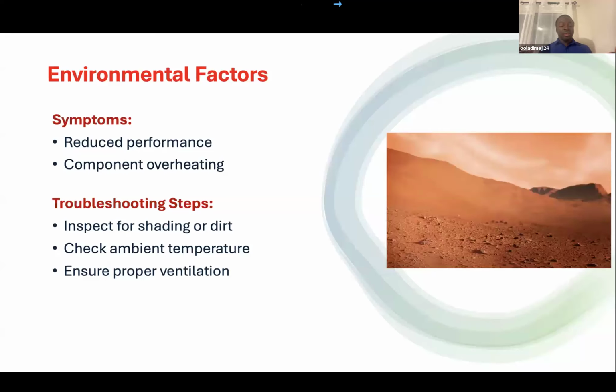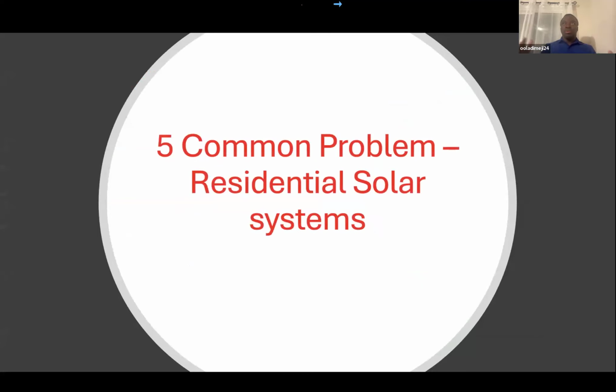You want to make sure that in the installation, there is aeration underneath the panels. If it's the equipment in the power room, check the ambient temperature and that where it is installed is good. Then you ensure proper ventilation so that the system can work better. So we've talked about individual components and the problems that we face with them. Like I said, these are the things that you see in a full solar system: the solar panels, the inverters, the batteries, the cabling. These systems come together, and when you have a full system, a part might not be doing its own job, and that will be causing the problem for you to troubleshoot.